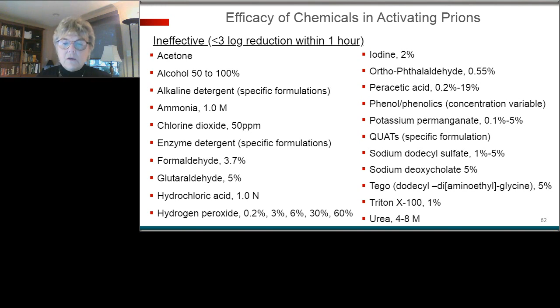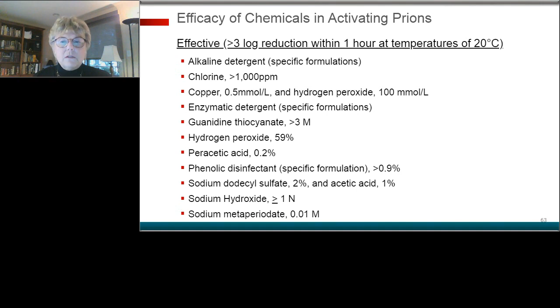Okay, so tell me what will work. And sometimes we'll see the same word, but with a higher percentage or a mixture. Alkaline detergents with specific formulations, chlorine at greater than 1,000 parts per million, copper, and you can go on and on with all of them, the peracetic acid again, but now at 0.2%. So there, you can deactivate them. You can deactivate them, but you need to know what to do. And the article that we are showing you, a SHEA guideline recommendation for prion-decontaminated instruments, would be an excellent source to really hone in on what you want to use.